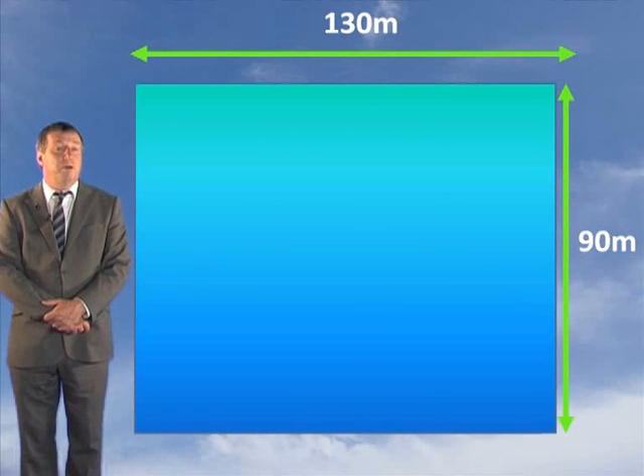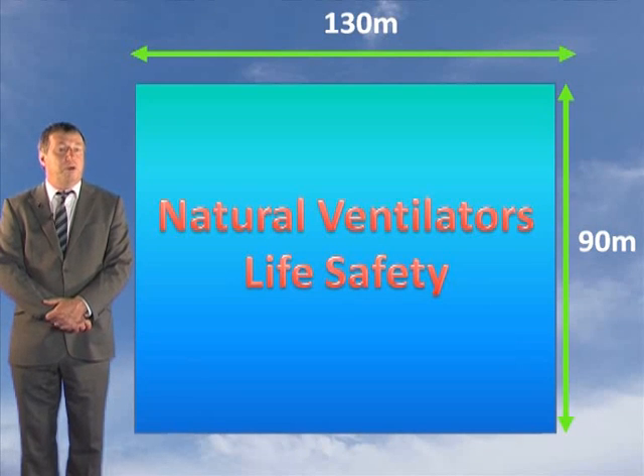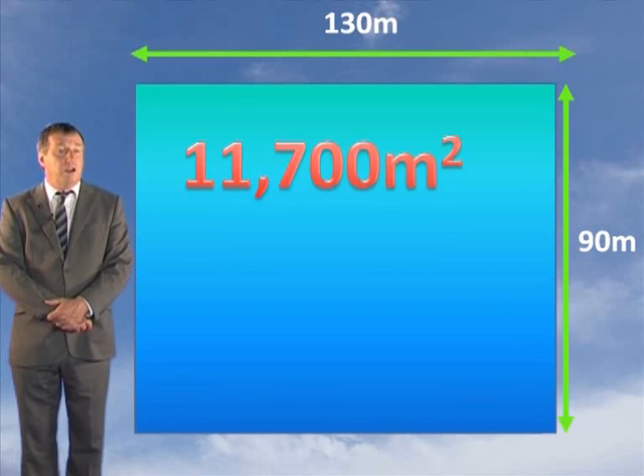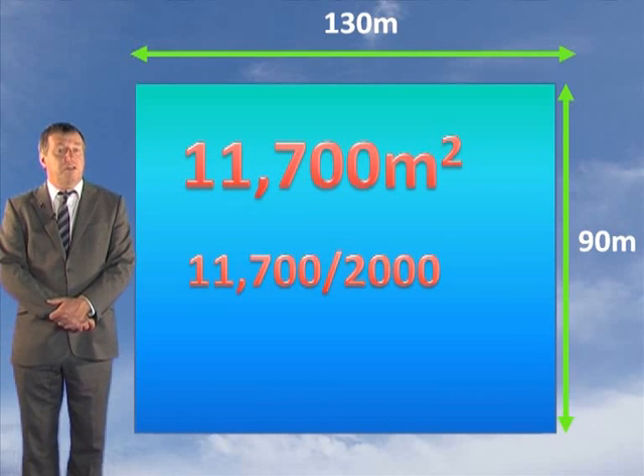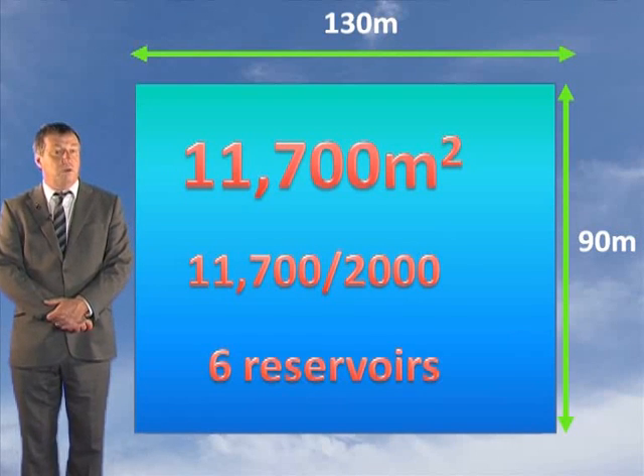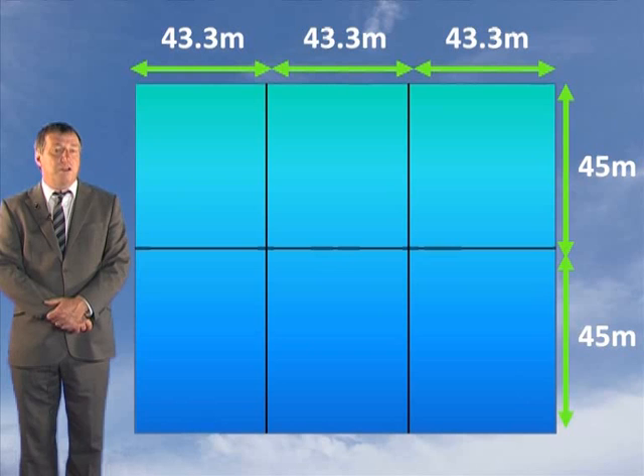Example two: determine the minimum number of reservoirs for a factory building 130 meters by 90 meters fitted with natural ventilators for life safety. The maximum size is 2,000 square meters and our building is 130 by 90, which equals 11,700 square meters. We need a minimum of six reservoirs, as five times 2,000 equals 10,000 which is less than 11,700, and six times 2,000 equals 12,000 square meters which is greater than 11,700. So we must have at least six reservoirs. We check that no dimension exceeds 60 meters with the aid of a sketch.